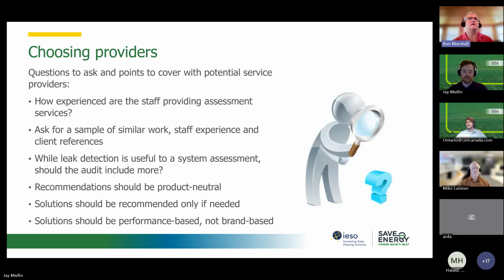Leak detection is done, but the audit should include more. So when you call an audit just leak detection, it's more than leaks. You need more than that. You need to know how those compressors are being controlled, so that you can get the best savings for your efforts, right? I always want recommendations to be product neutral so you can shop around, right? And should only recommend solutions if needed, right? If you've only got two compressors, really you don't need a very expensive compressor controller, right? Small compressors can work just fine with manual adjustments, right? And should be performance based, not brand based.